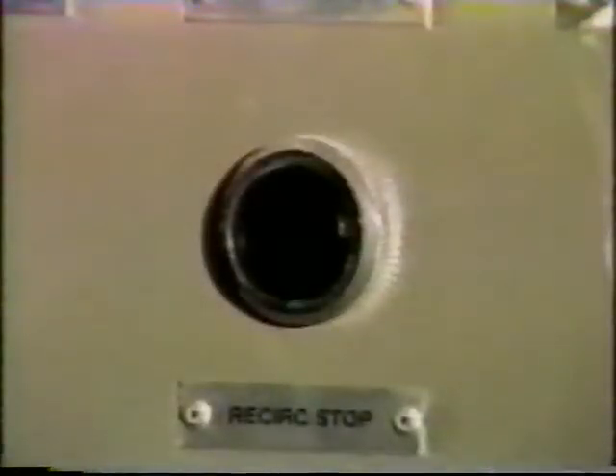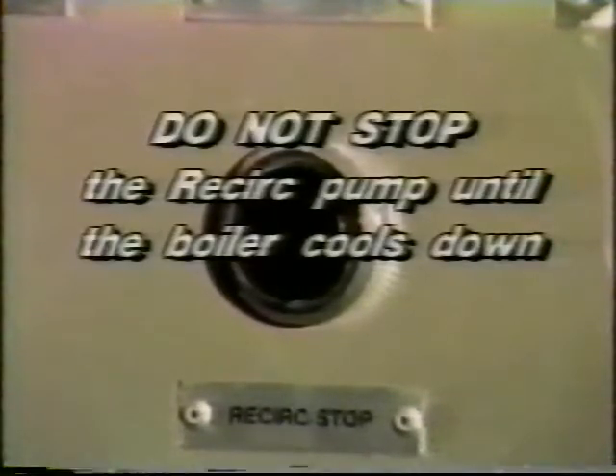Shutdown. Warning, the exhaust gas boiler cannot be shut down until the main engine is shut off. Once the engine is shut off, the recirc pump stop switch should be pressed to stop the pump. Do not stop the recirculating pump until the boiler cools down.